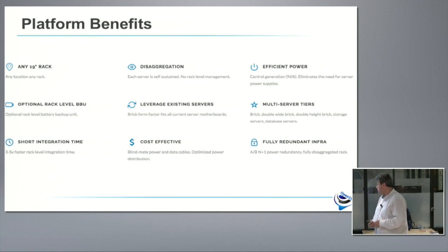They're completely independent, and we're extremely power efficient. The total rack efficiency is over 96% because of the power shelf distribution. We believe that by eliminating the power supplies from all the servers, we not only reduced the cost of the servers but also increased the efficiency at the rack level.